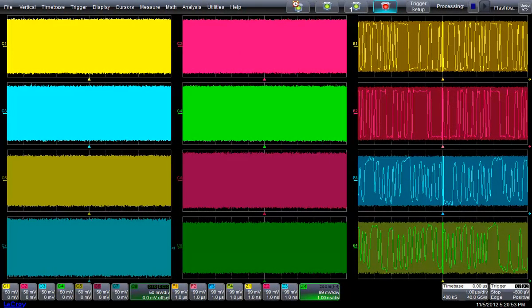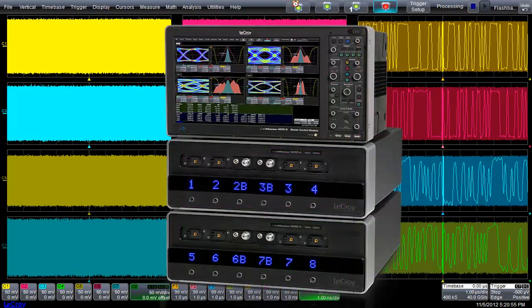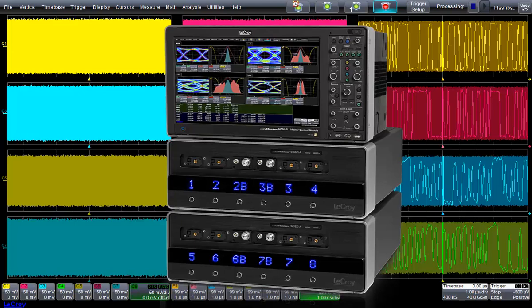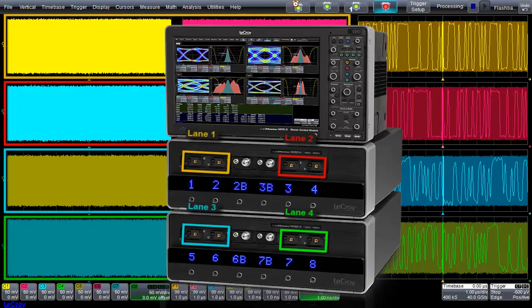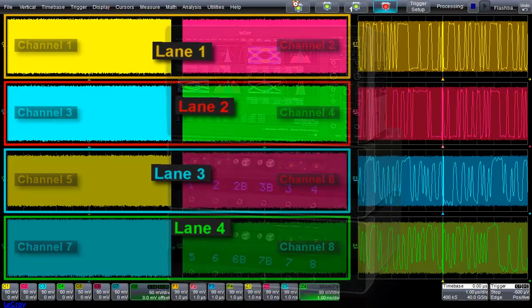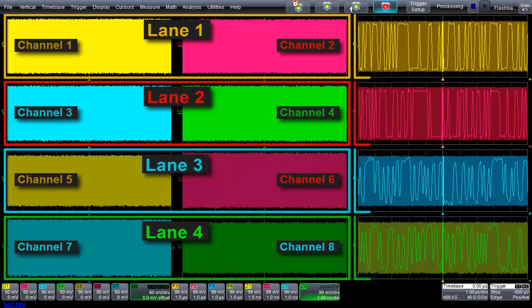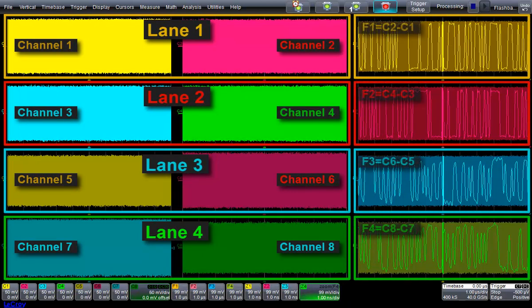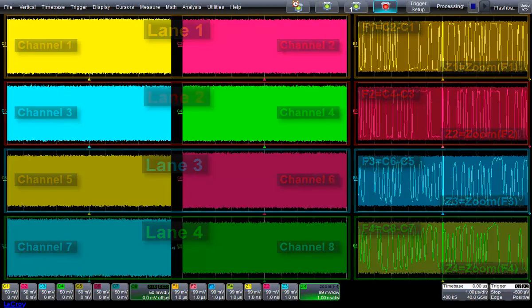Today, I am using a LabMaster 9ZIA real-time oscilloscope that provides 20 GHz bandwidth on 8-channel, sampling at 40 gigasamples per second. On the screen are acquisitions from four differential lanes carrying 10.3125 gigabit per second NRZ signals. The eight input channels are displayed, along with math functions showing the differential signal and zoom traces that give a better view at one nanosecond per division.